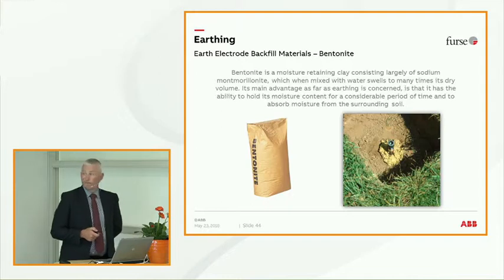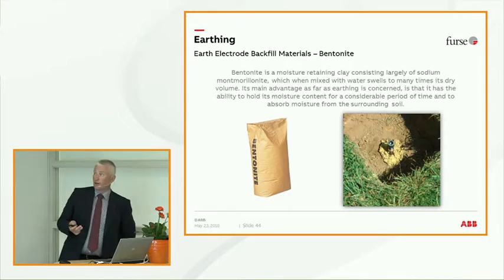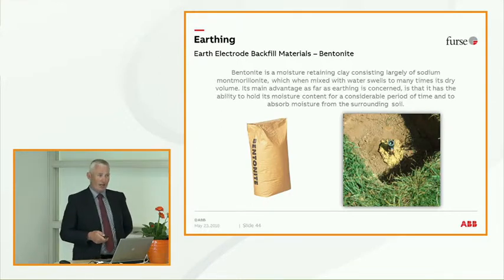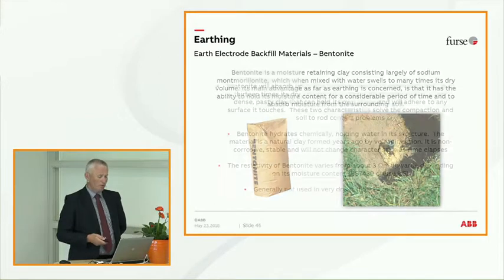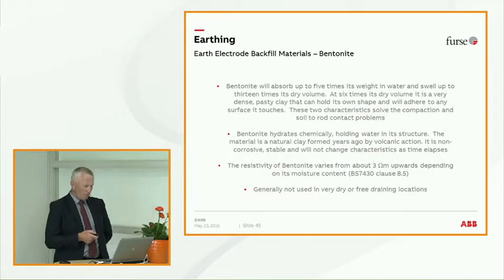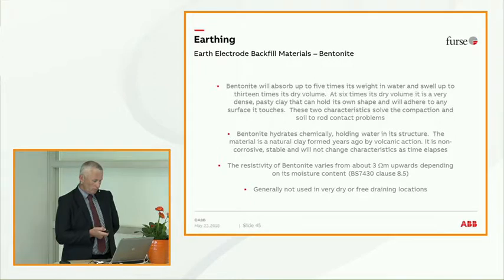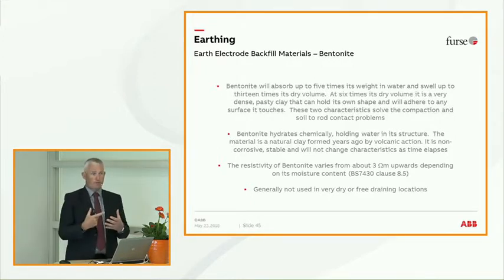There's bentonite. What bentonite is, it's a moisture retaining clay. It swells up 13 times its dry volume. It absorbs moisture from the soil, it keeps it wet, and it allows good conductivity. So when you're looking at that path to earth, this helps.